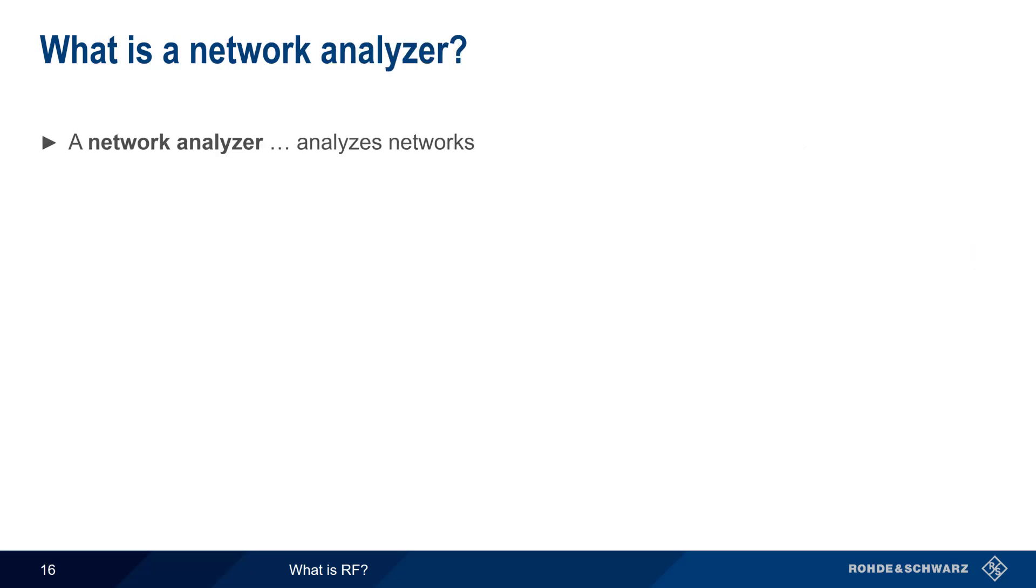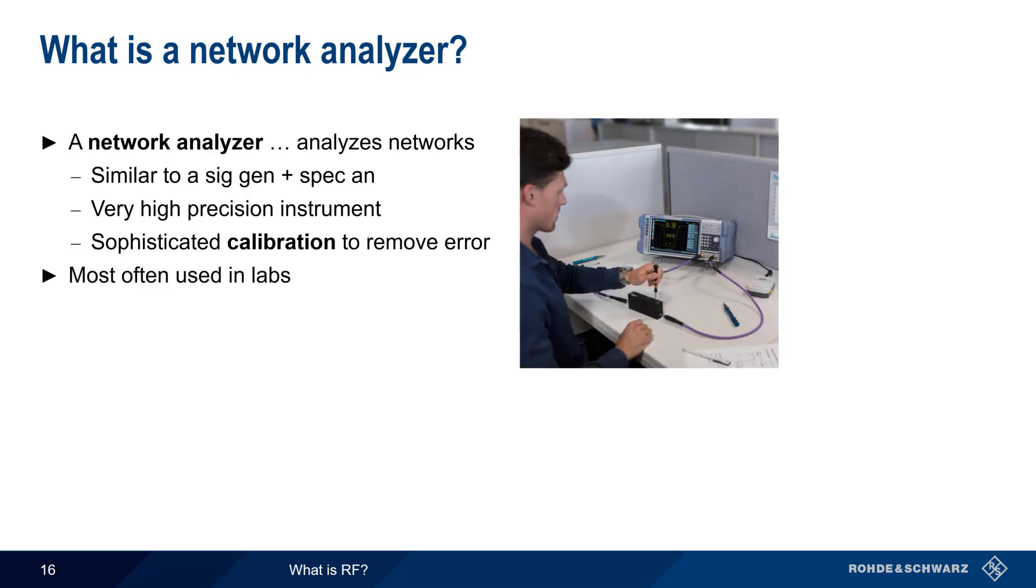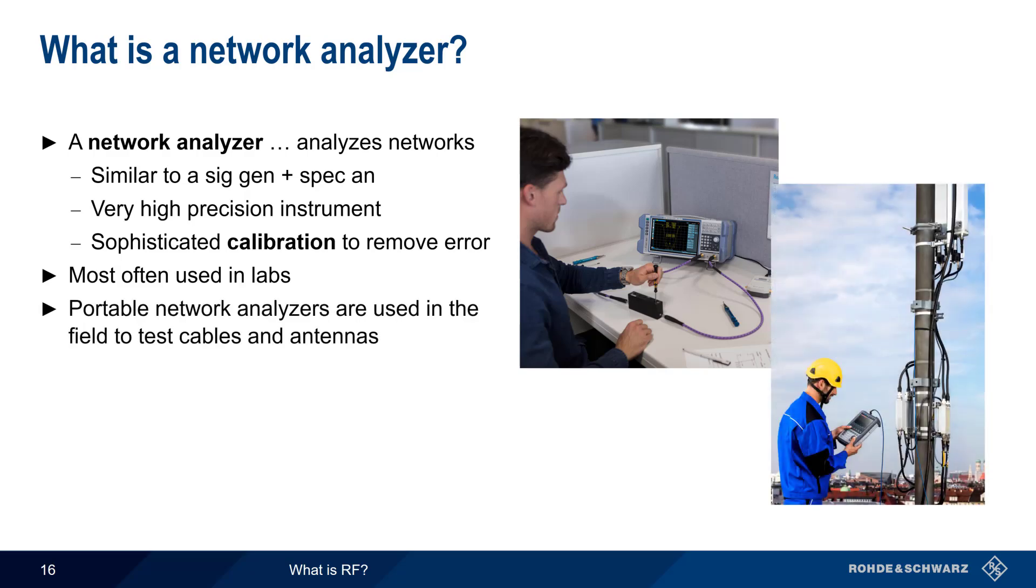In order to analyze networks, we use a network analyzer. A network analyzer both generates and measures RF energy simultaneously, and thus is similar to the combination of a signal generator and spectrum analyzer. In most cases, network analyzers are very high-precision instruments that are able to measure small variations or changes in signals, and sophisticated calibration routines are used to further minimize or remove error. Since they are most often used to measure components, network analyzers are most commonly found in labs, although portable network analyzers can be used in the field for testing things such as cables and antennas. You may also hear network analyzers referred to as vector network analyzers, or VNAs.